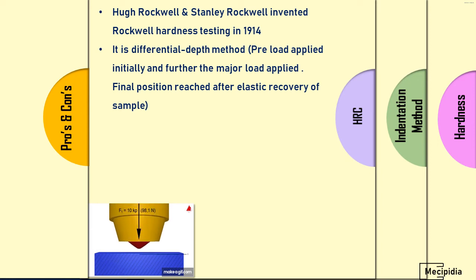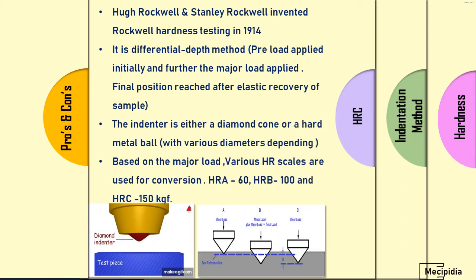It is basically a differential depth method. If you see the image below, initially a preload is applied and further the major load is applied. The final position is reached after elastic recovery of the sample. That particular differential depth is evaluated and shown as the final hardness in the display.